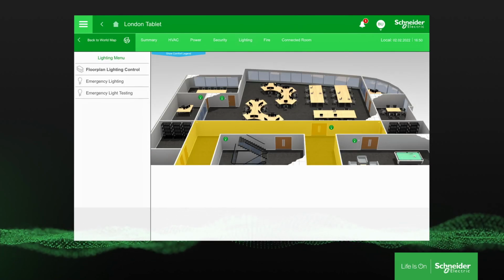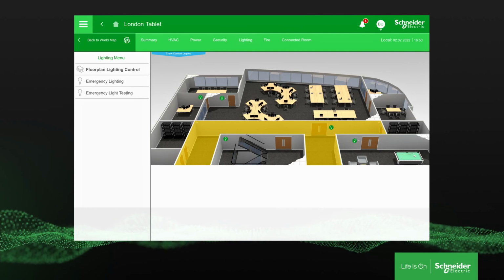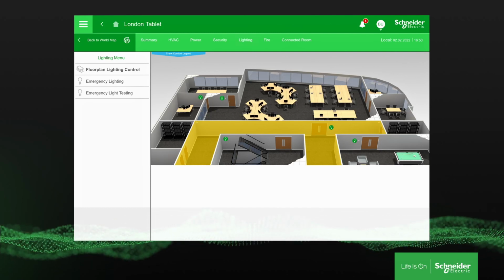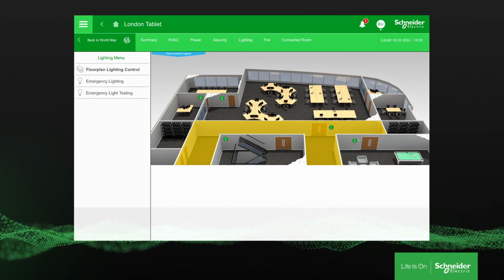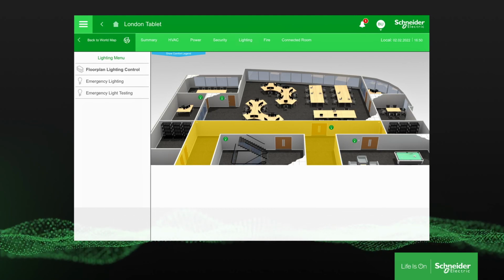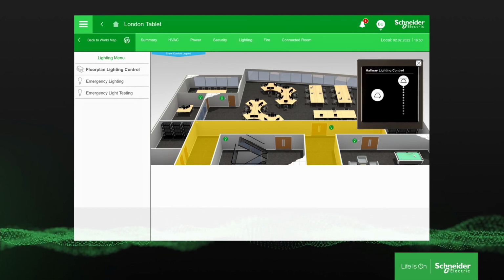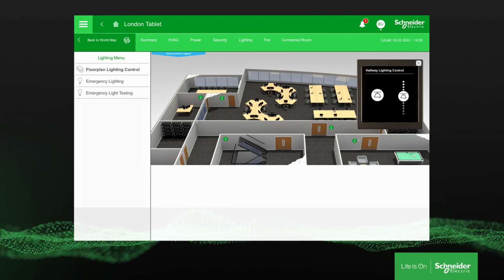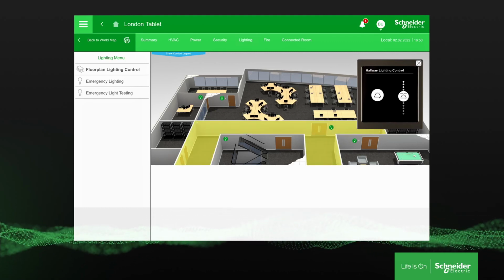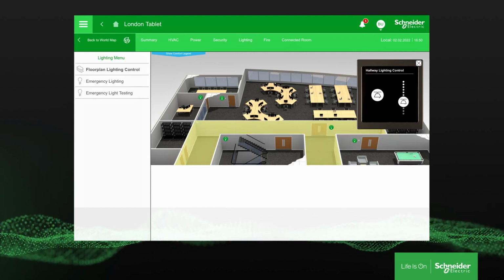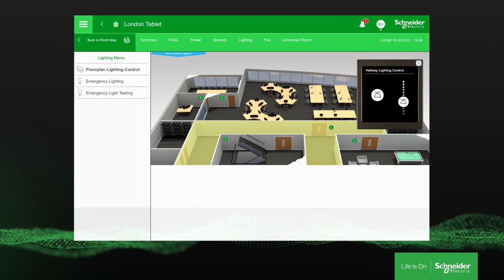Lighting control can be delivered in several different ways. EcoStruxure Building Operation might control it directly with local inputs or outputs, or it might interface with a dedicated lighting system using the DALI lighting control. In this case, we can control whether the lights are on as well as the level of light intensity. The floor plan can adjust the room overlays to give a visual indication of the current lighting level.